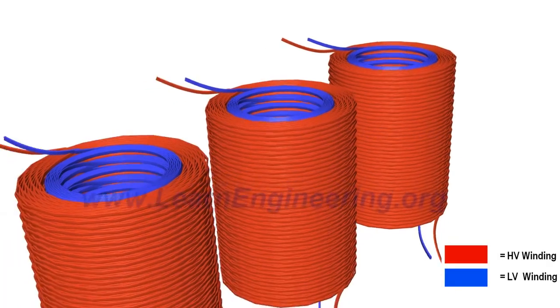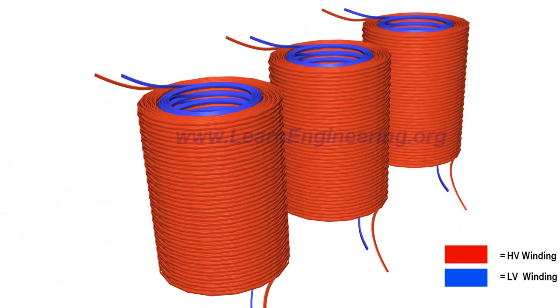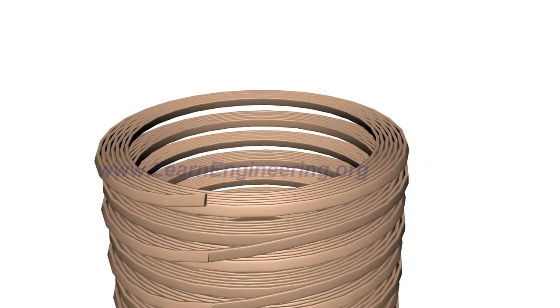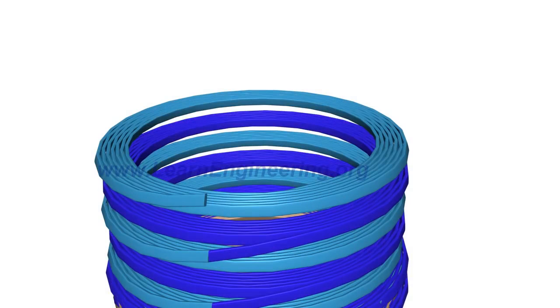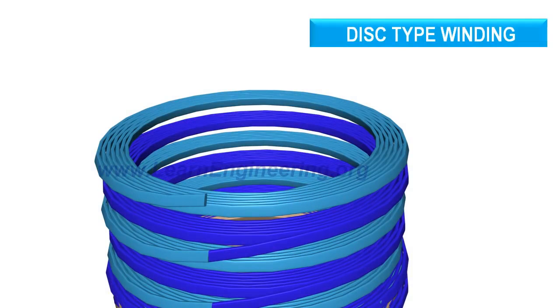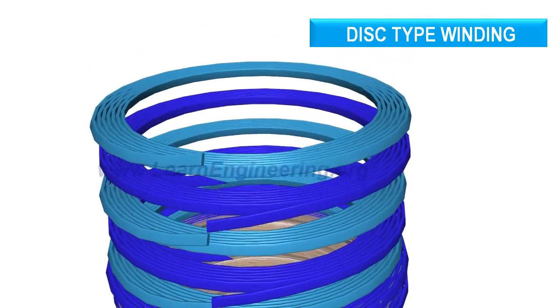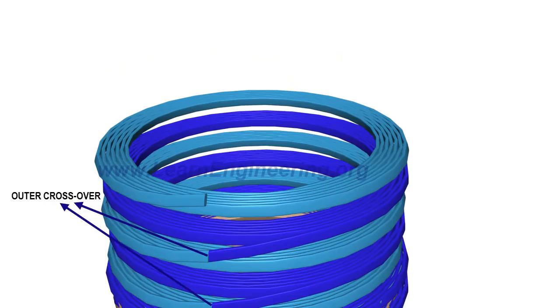Two more such windings are employed in a three-phase transformer. Transformers with high power ratings generally employ a special kind of winding known as disc-type winding, where separate disc windings are connected in series through outer and inner crossovers.